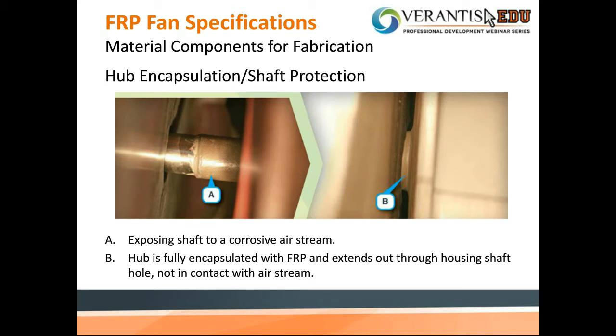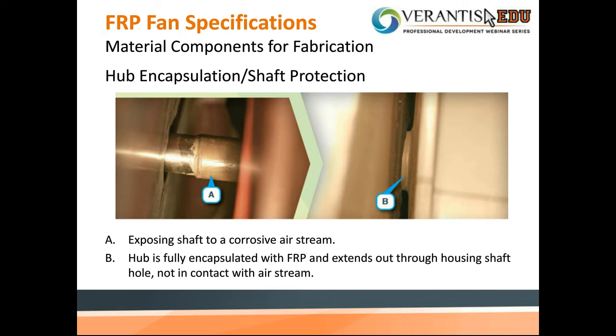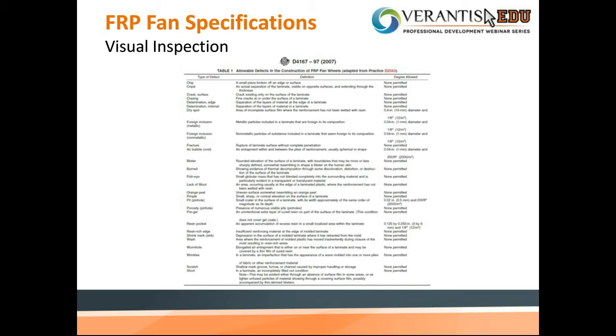Carbon gel coat meets the highest level of spark resistance. For fan applications and many other airstream applications, smooth interior surfaces help with airflow. Delamination or heat stress could affect product quality or surface quality. Two photos show a comparison of different quality levels in regards to fabrication and surfaces — it's pretty telling when comparing the two pictures side by side. We also supply sometimes Hastelloy or titanium alloys in place of 316 stainless steel bolting in severe corrosive environments, but internally those parts are still encapsulated in FRP.